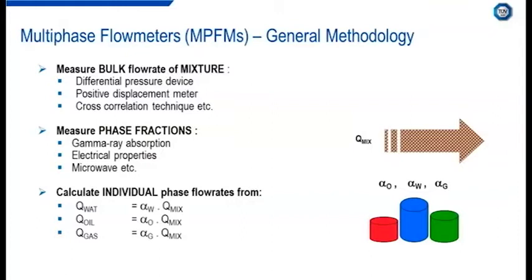So, the general methodology of multiphase flow meters. Multiphase metering technologies are required to measure oil, water and gas flow rates within a multiphase mixture simultaneously. The total bulk flow rate of the mixture is required, and common methods for the measure of the bulk flow rate of the mixture include the use of differential pressure devices such as a Venturi meter. The Venturi meter is the most common type of measure of bulk flow rates of multiphase metering technology. Positive displacement meters could also be used, however are far less common in multiphase metering technologies available in the market today. And cross-correlation techniques have also been used and could be considered for bulk flow rate measurement of the mixture.